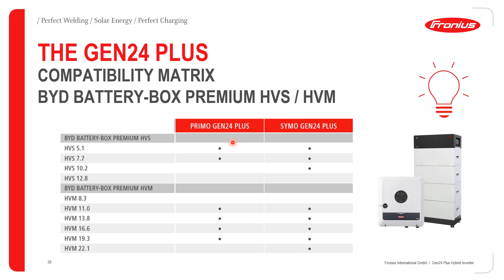So in terms of the backup operation, the way it works is quite straightforward, but you do need to configure a backup panel, because once there is a grid cut, this backup panel opens and closes some contacts, and a signal is sent to the Gen24 Plus inverter, and that signal is the one that allows the Gen24 Plus inverter to go into backup operation mode. For that purpose, you also need a Fronius smart meter. You are not able to configure full backup operation of the Gen24 Plus inverter without a Fronius smart meter. So there is a communication that is required from the Gen24 to the smart meter, as well as from the backup panel, for the Gen24 Plus inverters to be able to go into full backup operation.